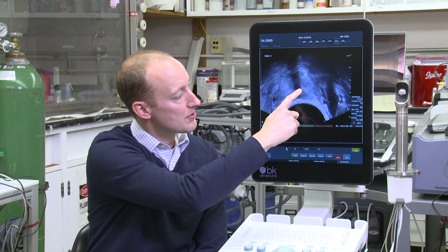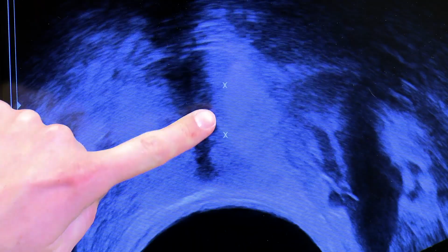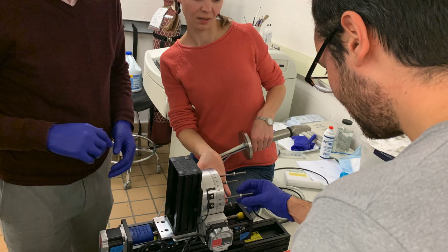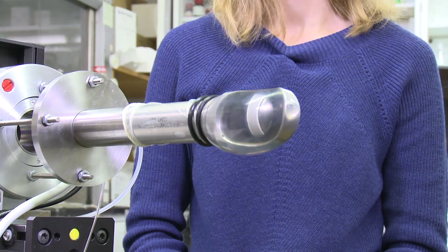So in order to treat clinically relevant volumes with BH, we had to come up with a system to position our focus in three-dimensional space. For that, we put together the system that you see here. It includes the therapy probe and the imaging probe in the middle. It has the coupling balloon that is inflated with water, and it can change the position of the focus in tissue by inflating or deflating this water standoff. A 3D positioning system can position the focus with sub-millimeter precision in the axial direction and in the angular direction.